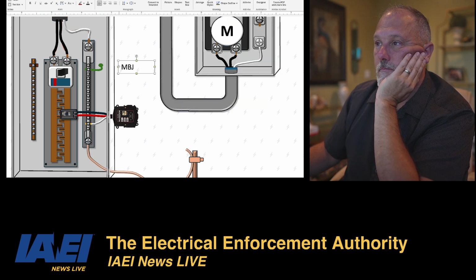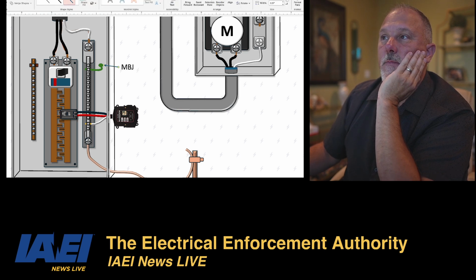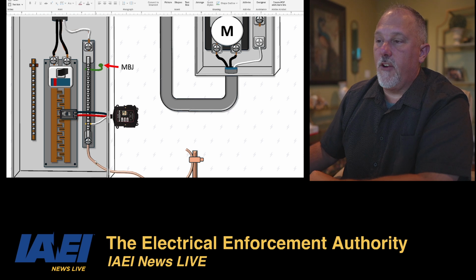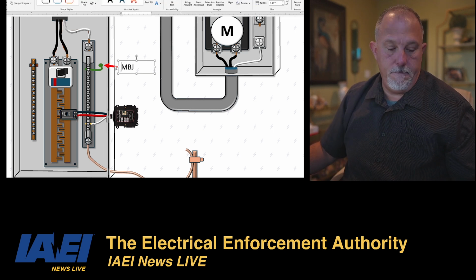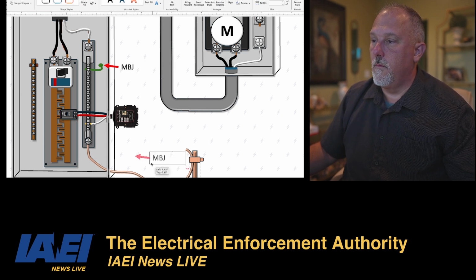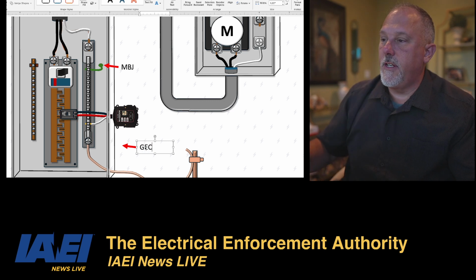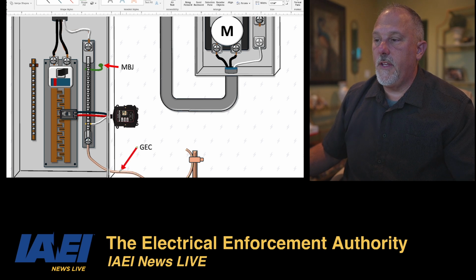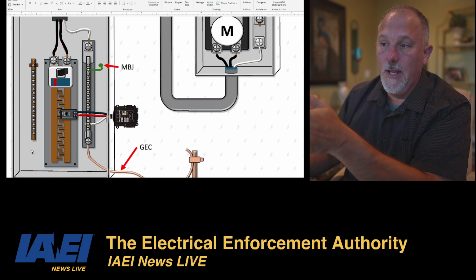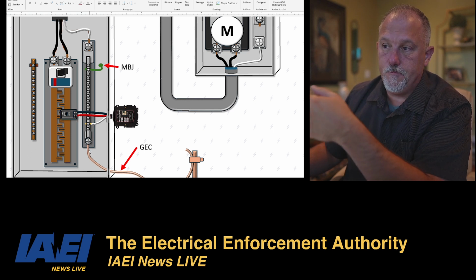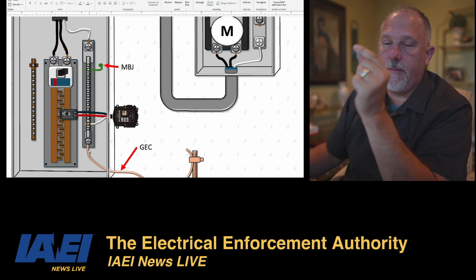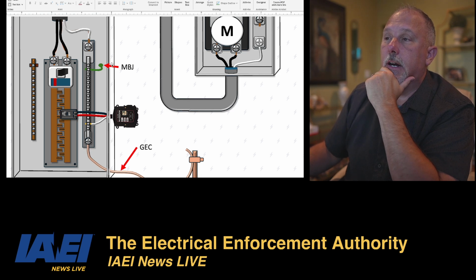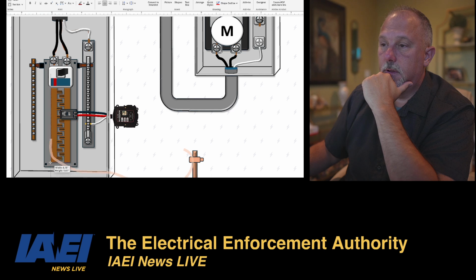So that's my main bonding jumper. Let's make this thicker. All right, my grounding electrode conductor, my GEC, would be this conductor here, and it has to land on the neutral bar because I cannot use the back pan between my GEC and my neutral bar, my grounded bar. Again, unless I did this. Now I can do that.